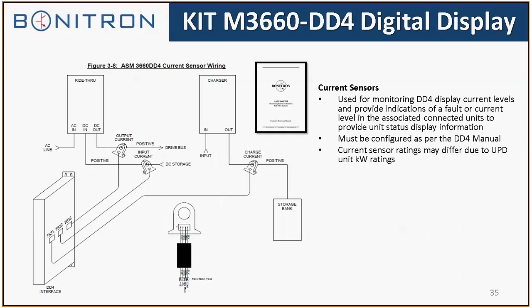As you can see, the connectivity goes between the DD4 interface module. Current sensors connect to the ride-through bus to be able to monitor the DC bus voltages, and it also monitors the charger charge current, and it shows you the pinout for the actual current sensors in the bottom of the page. That's all included in the manual that's indicated by the icon.